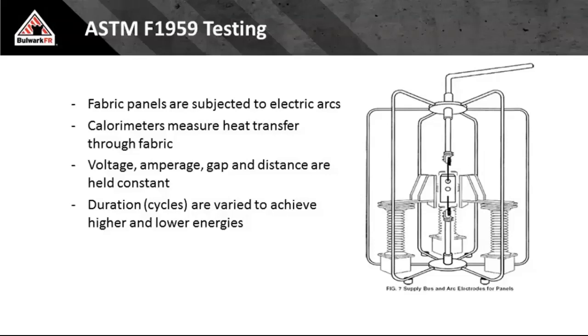The demarcation point is roughly about 1,000 volts. So if I'm looking at a 480 panel, I'm going to assume that puts me into Cat 2. That's my hard hat, face shield, rubbers, leathers, balaclava, hearing protection, eye protection, and insulated tools. And I go to work on that box.